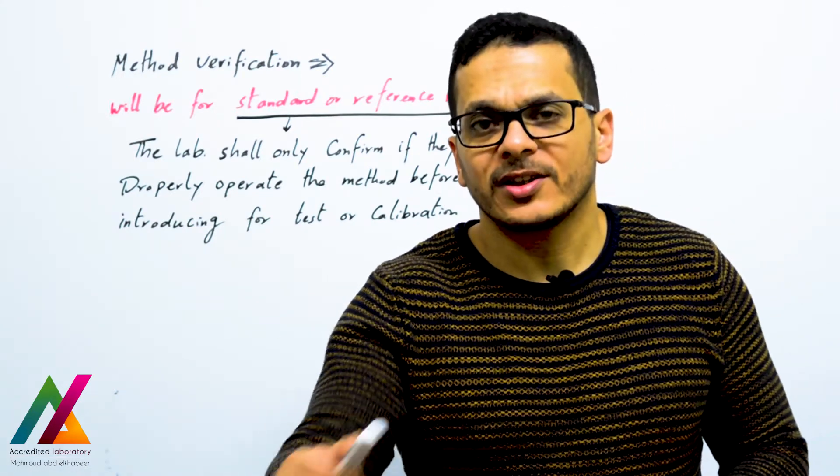If you made a minor change to the reference method, you don't need full validation — you just need to make verification. This is because a reference method has already been validated by a group of laboratories who carried out the validation before it was published as a standard. So it's already validated, and you just need to evaluate some performance parameters.